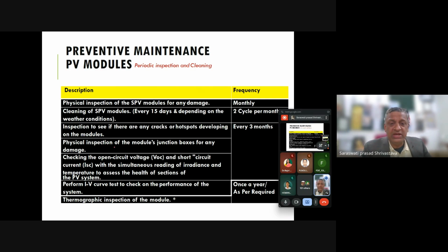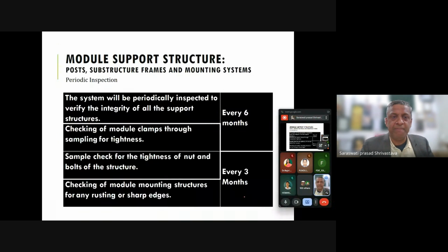Third thing, physical inspection of module junction box, if any, checking open circuit voltage, short circuit current, instantaneous, every 3 months we have to do. Perform IV test, this requires a bit another skill, so we can do it only once a year. Thermographic inspection of the module, the set is already connected, so you only need it once a year.